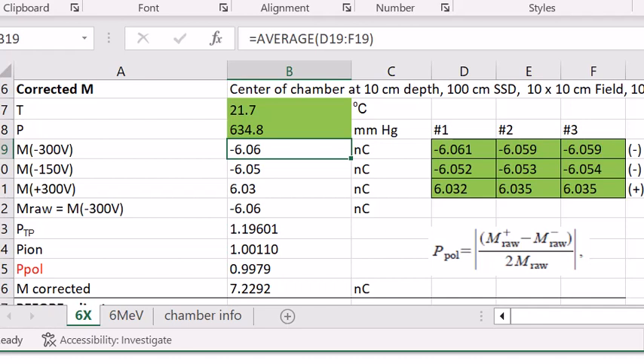And you can see that our P-polarity factor in here is 0.9979, which should be very close to 1. 1 means our chamber is ideal. Basically it means biasing sufficient positive and negative volts, 300 versus negative 300, will not make a difference.